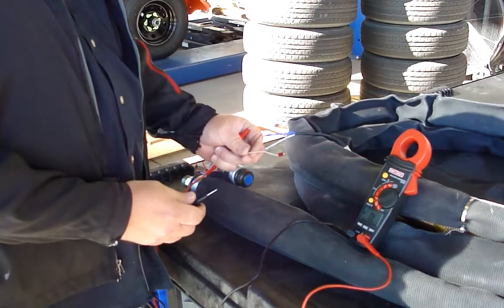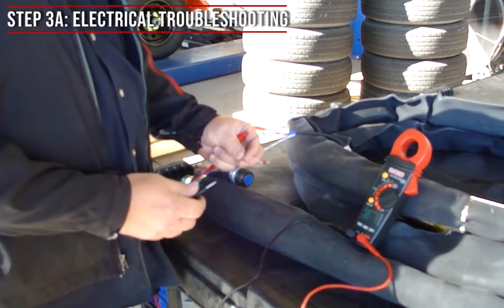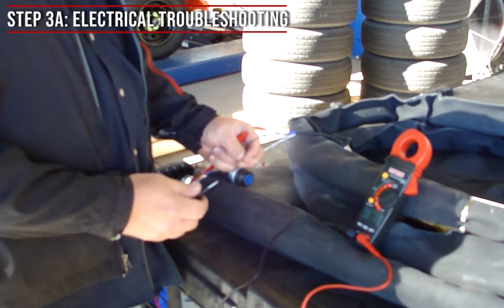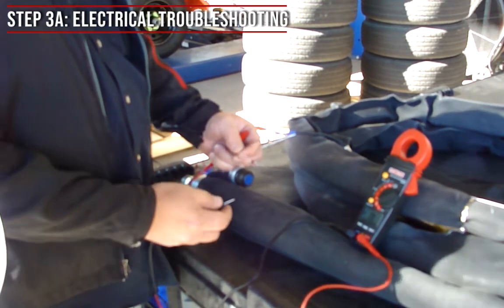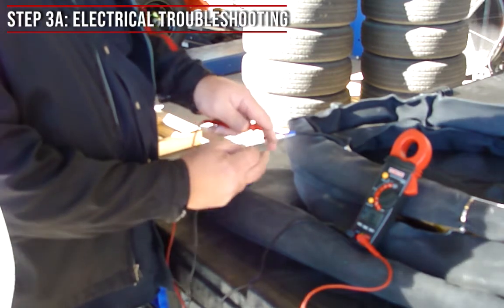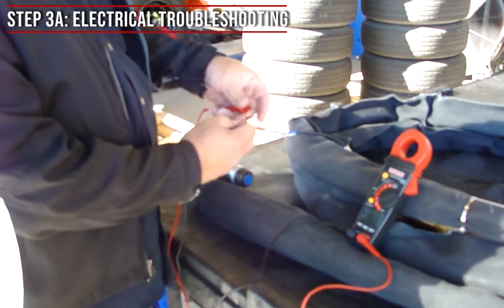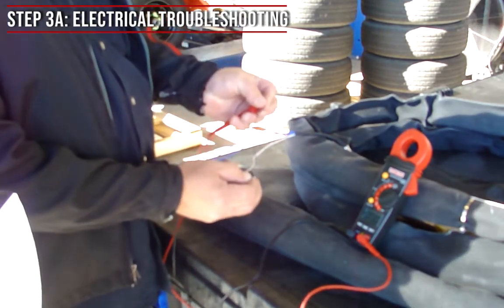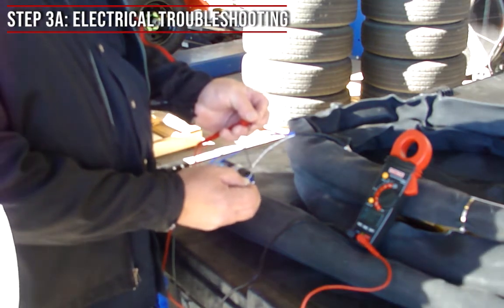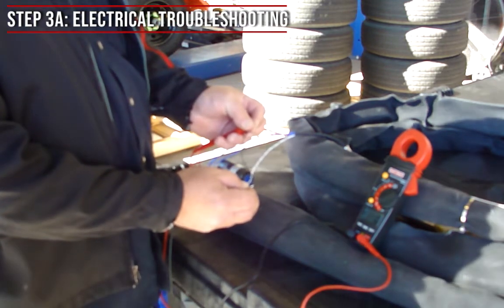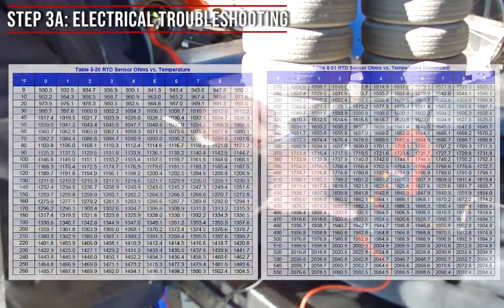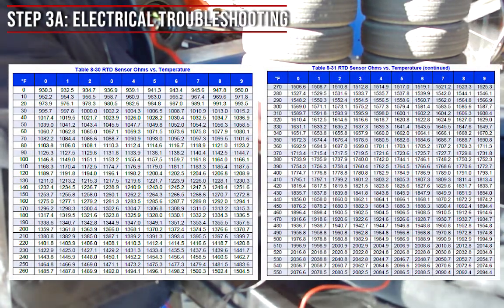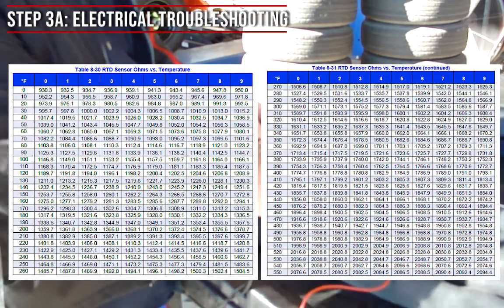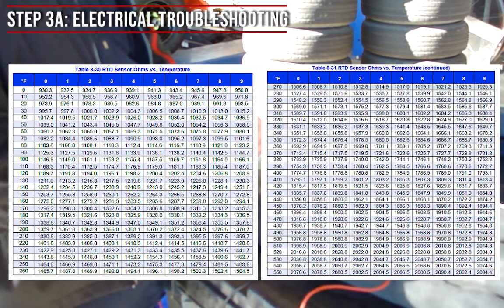Step 3A, electrical troubleshooting. Now we're going to check the RTD sensor by disconnecting the black and white wires from the terminal block in the junction box and test for ohms. You're testing the black and the white wire at the same time. One lead is on the white wire and the other lead is on the black wire. Compare the ohms and the temperature in the ohms chart. This is shown here in this image. This chart can also be found in your operating manual.